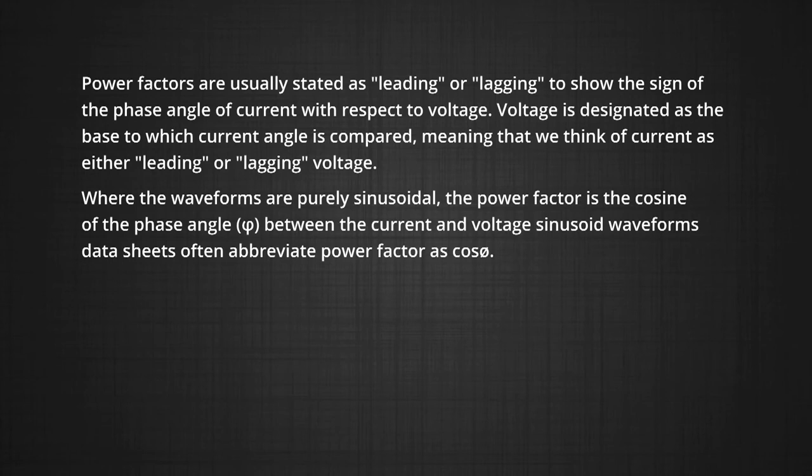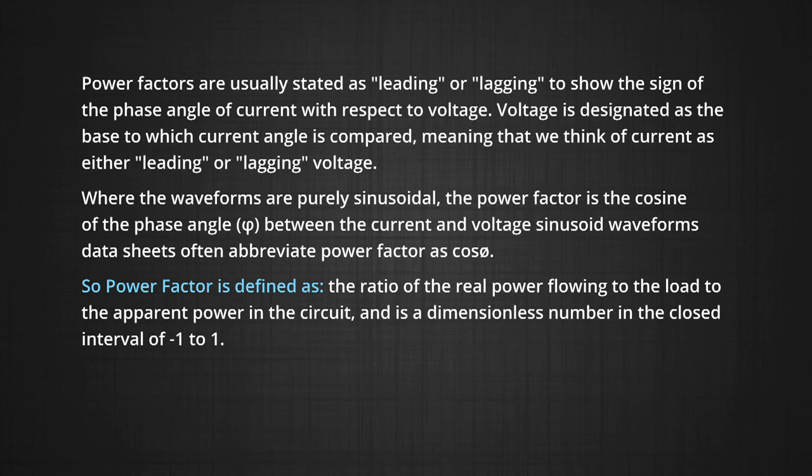Where the waveforms are purely sinusoidal, the power factor is the cosine of the phase angle phi between current and voltage, that is the sine wave or sinusoidal waveform. The data sheets often abbreviate power factor as cos phi. Power factor is defined as the ratio of the real power flowing to the load to the apparent power in the circuit and is a dimensionless number in the closed interval between minus one to plus one.